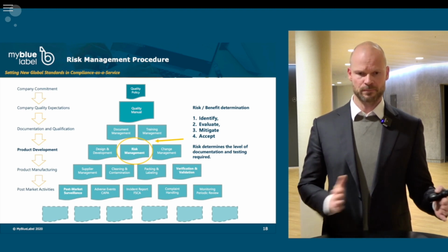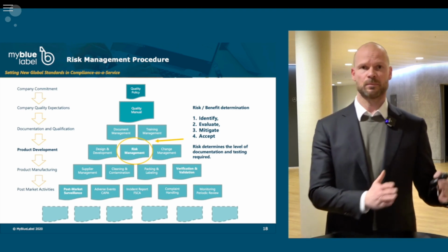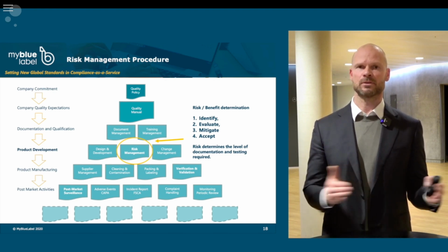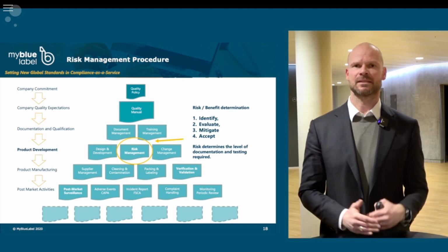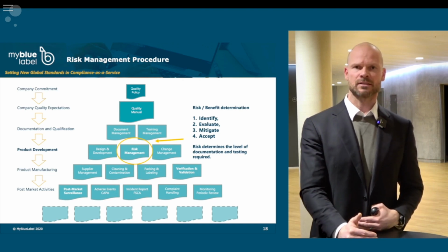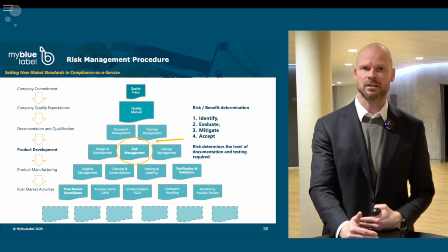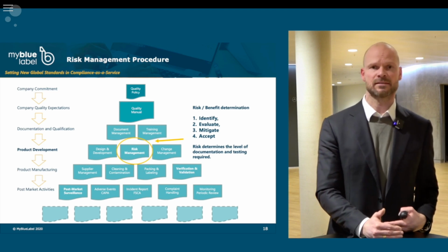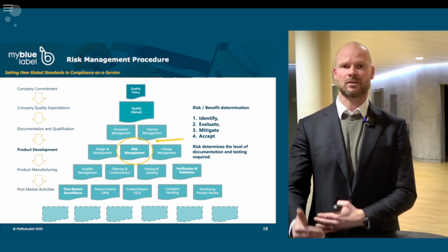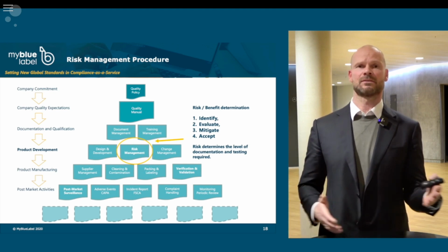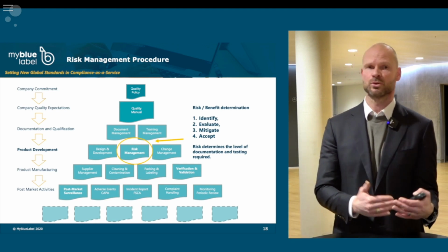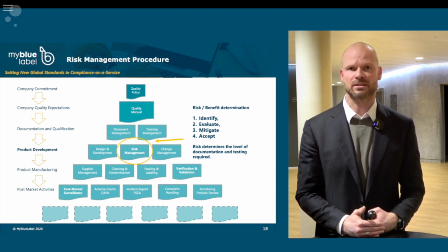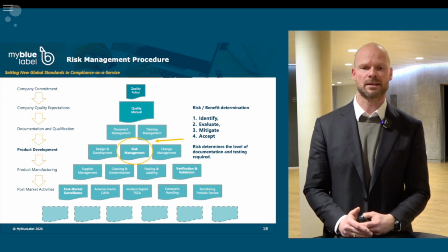So currently, based on regulation, risk is really important, but also based on performance and an effective business, it's important to be able to align risk with incidents and see, are we really focusing on the right activities in the company. Typically, a company will find 100 or 200 risks on a device, but in an incident or post-market surveillance phase, you will get 10 to 20 different incidents. So possibly you could work better with the last risk, or downgrade the risks, so you're focusing on what really matters.